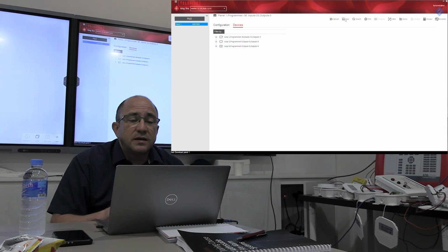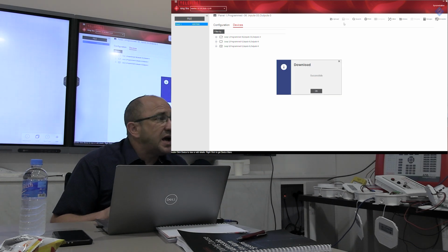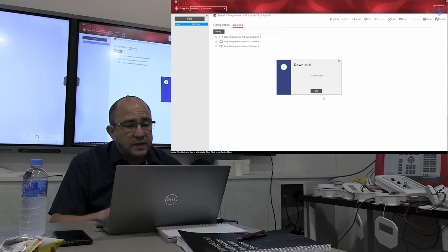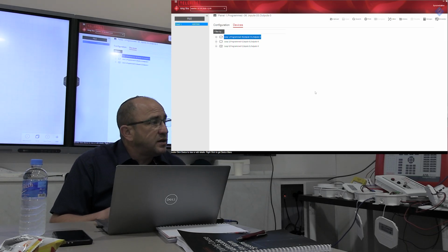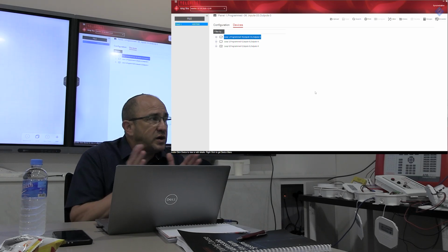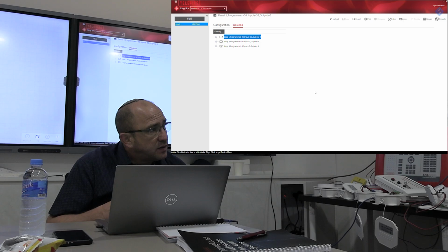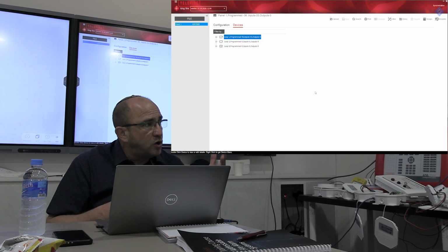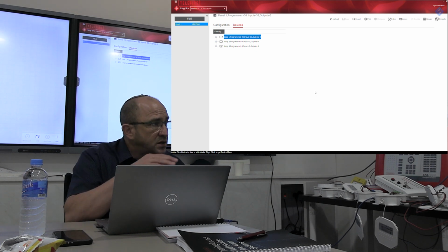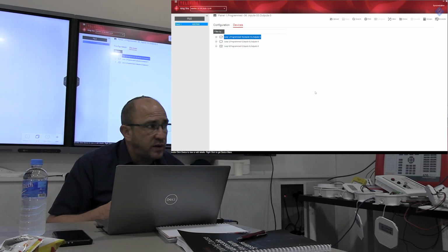What does the safety guy want? Does he want that the flow switch will be like a push button, or the push button must work like a detector? Is the flow switch work like a detector? A flow switch? No. Flow switch has priority. So if I do 2 alarms or 3 alarms from detectors, the flow switch will work automatically, straight away. Because flow switch means there's fire in the building.